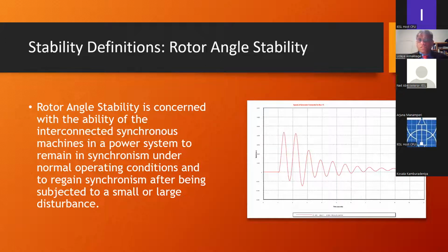And one can elaborate on this for hours and hours. I just included a trace of the speed of a synchronous generator. This came from one of the simulations. This is when a short circuit fault happened in the system and the fault was cleared. And then the synchronous generator, this particular generator, stabilized. We can see a few large swings in speed, and then the amplitude of these swings getting smaller and smaller in an exponential manner, and it settles at a new equilibrium. And if you pay attention, you can see that the new equilibrium is not exactly the same as the original speed of the machine, slightly higher, but as long as it's within the limits and steady, it's considered stable.